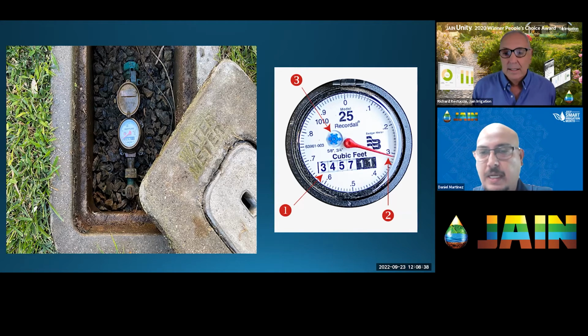There's a couple things - one, if you look at the gauge on the right-hand side, zoomed in, that number one arrow is pointing to the totalizer. That's giving you a total of how much water you've used over the life of the system. This is what your meter company comes out and reads every month to determine how much water you're using, to send your bill. Number two is the flow indicator needle, which also totalizes - one full turn will give you a cubic foot in this case.